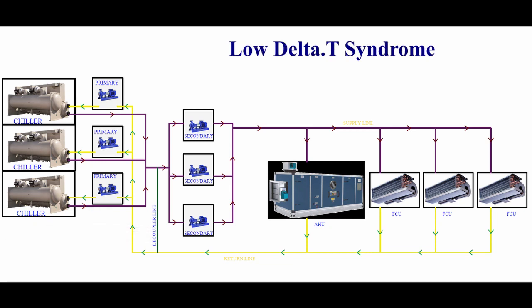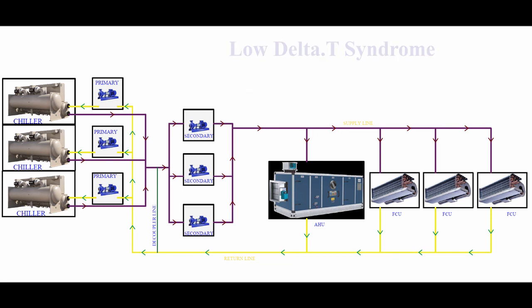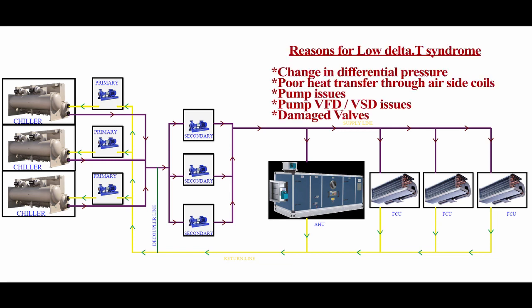The reduction in chilled water temperature range is called low delta T syndrome. Not only due to changes in differential pressure — this can happen due to various reasons: if the heat transfer through the air side equipment coil is not proper due to air contaminants or dust, or the flow rate of water through the coils is too high, or any problems in the pump variable speed drive, or problems in the control and balancing valves — all these cause low delta T syndrome.